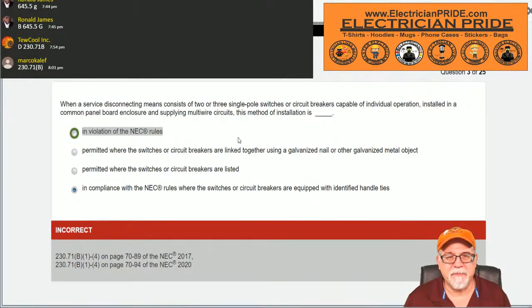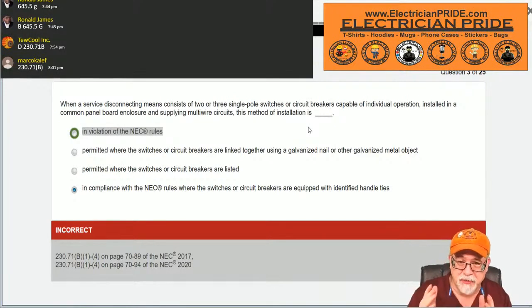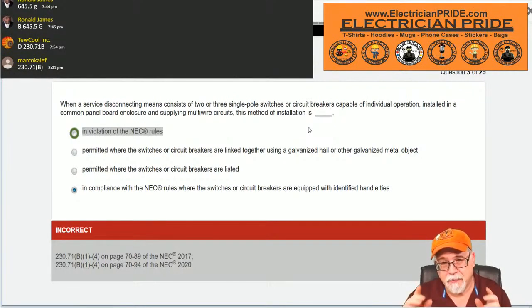But again, it's a violation to do so. Now, not for the multi-wire branch circuits, you're okay to use 2 poles, single pole, or 2 single poles with an identified handle tie. Those are okay. This question wasn't about the multi-wire circuits, it was about the service disconnecting means. So y'all were good at the right location, just chose the wrong answer.